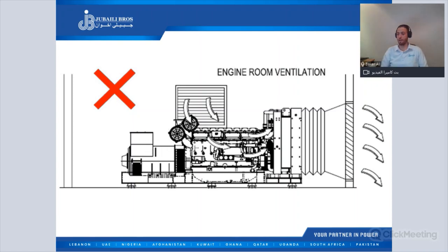With this ventilation system, this will increase the operating temperature and will cause overheating for the generator. So this system should not be considered. This system is wrong and should not be considered. Again, the airflow here will bypass the alternator and the air filters, will pass directly to the engine, to the radiator fan, and then outside the generator room. So this one should not be considered.